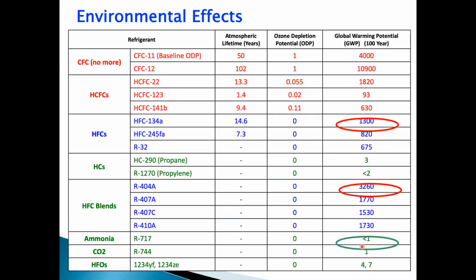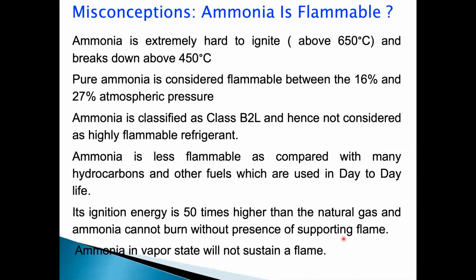As I was talking about environmental effects, ammonia as compared to HCFCs, CFCs, HFCs, HCs, everything you compare, ammonia is the best one. It has zero ozone depletion potential, less than 1 global warming potential, considering the 100 years effect. The only one that comes near to ammonia is CO2, which is a natural refrigerant. But in India particularly, CO2 has limited application because CO2 pressures are very high, and we have to go for cascade systems when using CO2. So considering the cost of the equipment and the running cost, ammonia becomes the most efficient.